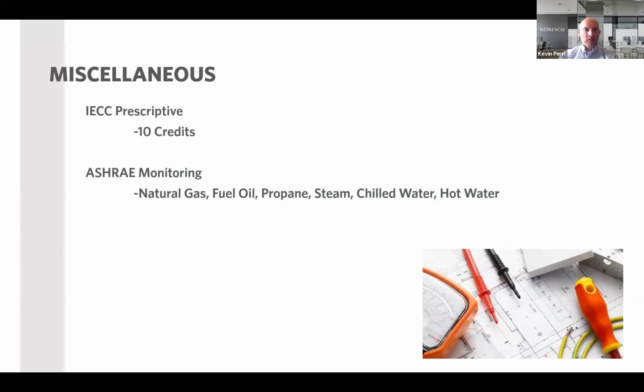So the other miscellaneous items, if you're following the IECC prescriptive path, if you remember section 406, that was a category where you had 6 or 8 options and you had to pick one to go above and beyond as an additional energy efficiency option. They've now said it's based on credits. So if you wanted to do 10% better on your lighting power density, that's great. But that might not be enough energy efficiency measures to get to the 10 credits. So that might be weighted only 1 credit, so you might need to do another credit. So just know that there is a miscellaneous category for following the prescriptive in IECC that requires you to get to 10 credits in there. And there's a bunch of tables to look at to say, I'm going to do this one, and this one, and that's how I'm going to get my 10 credits.